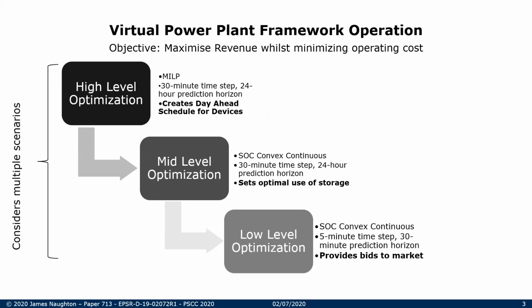This schedule is then passed down to the mid-level optimization, which conducts a preliminary economic dispatch problem with a 30-minute time step to attain an optimal use of storage over the coming 24 hours. Because the value of the integer variables was set at the high level, this is now a continuous optimization.